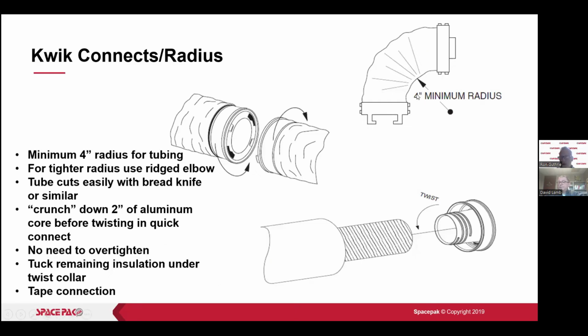Minimum 4-inch turning radius. Basically our fittings are quarter turn. We screw these in. The other end of this takes a quarter turn for a tight seal to go onto the end of this. So you cut your own length, you put the quick connects on from the installation kit, and then a sound attenuator would go on the end. So basically, if this was the duct that you made up, the sound attenuator would screw right onto that. The 2-inch outlet would screw right onto the end of the sound attenuator by that quarter turn twist, and that would be a tight seal.